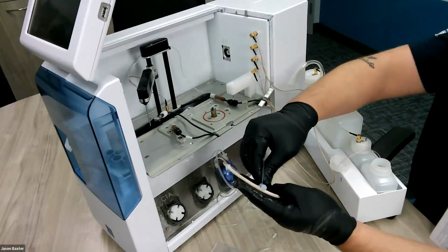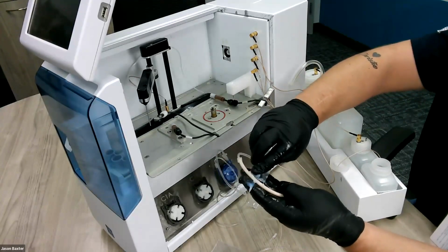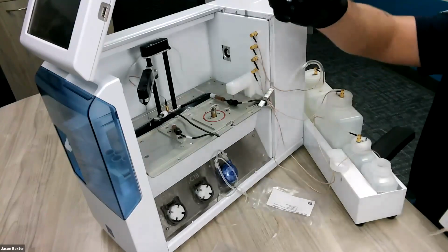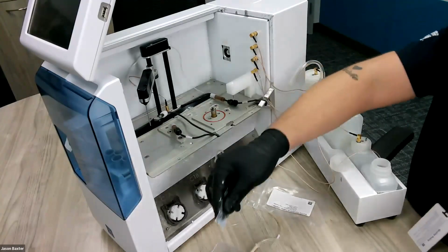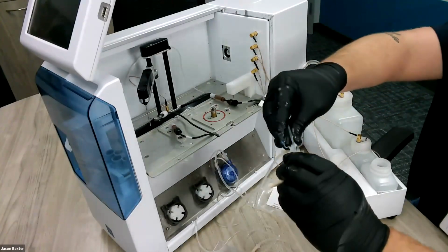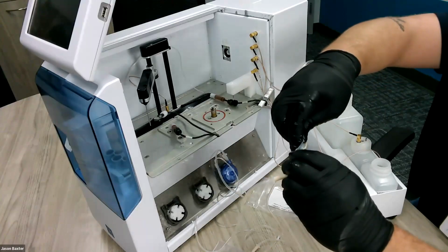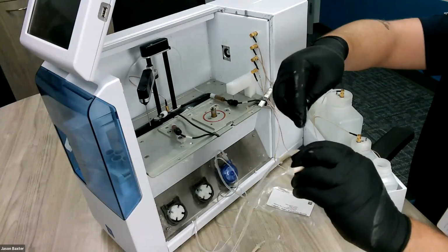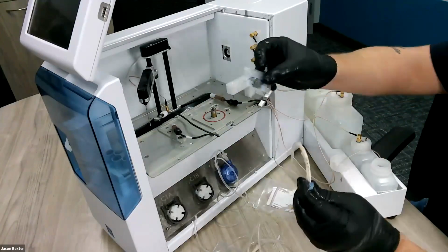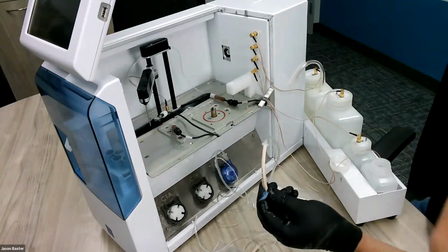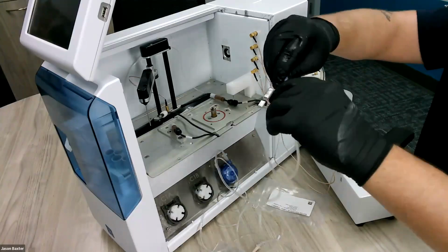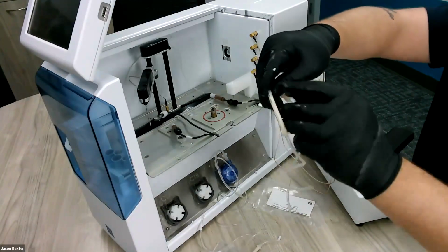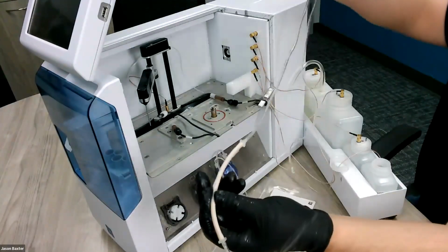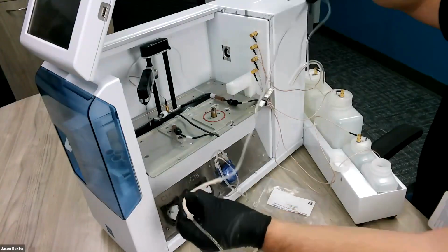So again, you want to use about half of that grease pack on 1B and the other half on 1A. That's the reason we only give you one grease pack for the 2 calibrator tubes. The expectation is you're going to use about half of this packet on A, half of the packet on B. Again, slather it up. Make sure the inlet side is on the right-hand side.